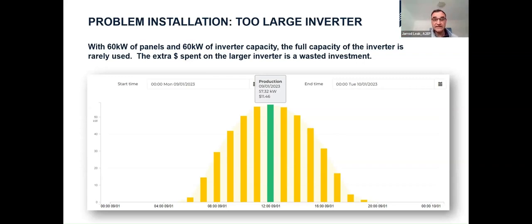This is for 60 kilowatts of solar panels and 60 kilowatts of inverters, and in this case it really doesn't even use the maximum capacity of the panels. Ideally, in the middle of summer you'd be maxing out around 11am to 1pm, and if you had, say, 50 kilowatts of inverter, the extra few thousand dollars spent going from 45-50 kilowatts up to 60 would give very little extra production. So you'd spend a couple of thousand dollars too much on inverters, which could have gone into your back pocket for better things. Just something to keep in mind.